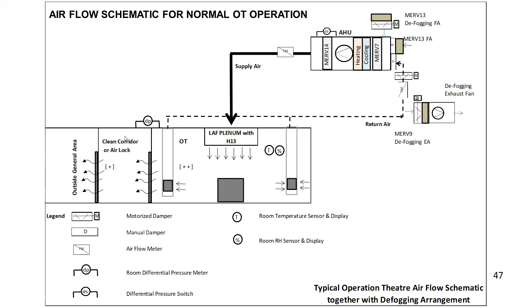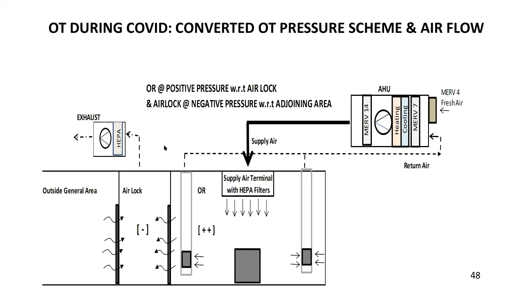So what we have to have is that the airlock has to be under negative pressure. So air moves from the operation theater into the airlock. Similarly, the outside general area, the air moves into the airlock, and this is through a HEPA exhaust. This is what is the recommendation. So this is for the COVID times.